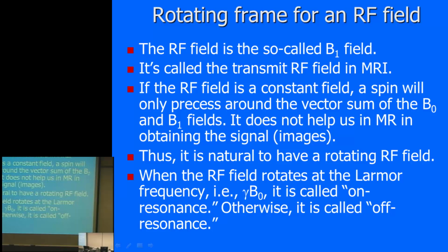But sorry, that's not completely true. I'm just saying that from the mathematical point of view it's this, but from the physics point of view, I will tell you more later. Say 10 minutes later, you will see why this is important. I want to design my RF coil such that it resonates. One technical way to say it is that I need this RF coil to resonate at the Larmor frequency. In other words, when I'm in that frame, I can see the proton as if the proton is not moving. That's the purpose for this RF coil.